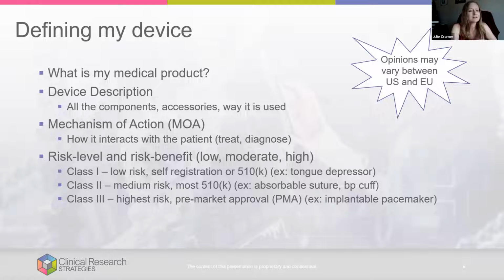Then there's class 3, the highest risk. This will automatically require a pre-market approval or a PMA versus that of a 510K. It requires the highest amount of clinical evidence compared to the 510K or compared to the other two classes. And it's something like an implantable pacemaker. The risk is high for the patient, even if it's used correctly. And then if there's misuse, the risk is even higher.